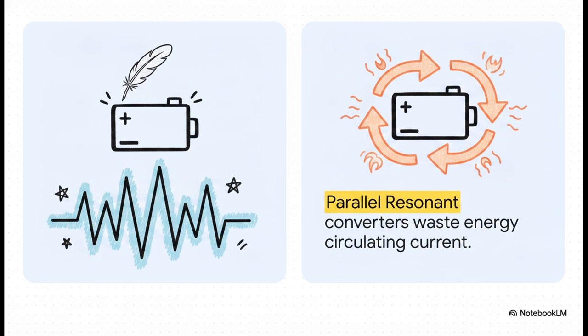With conventional series resonant converters, if your load is light, meaning the battery doesn't actually need much power at that moment, the system practically needs infinite frequency just to regulate the output. On the flip side, parallel resonant converters waste a massive amount of energy just circulating current within the system itself, which makes them completely impractical for high-power UPS battery charging.